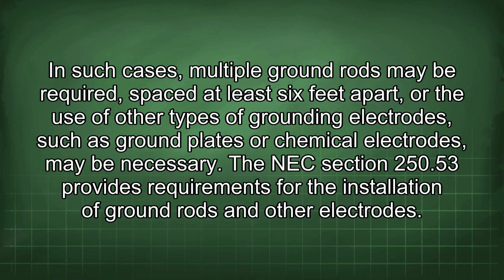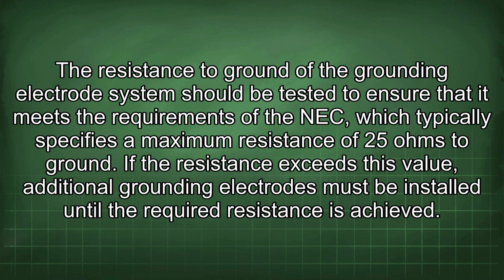The NEC Section 250.53 provides requirements for the installation of ground rods and other electrodes. The resistance to ground of the grounding electrode system should be tested to ensure that it meets the requirements of the NEC, which typically specifies a maximum resistance of 25 ohms to ground. If the resistance exceeds this value, additional grounding electrodes must be installed until the required resistance is achieved.